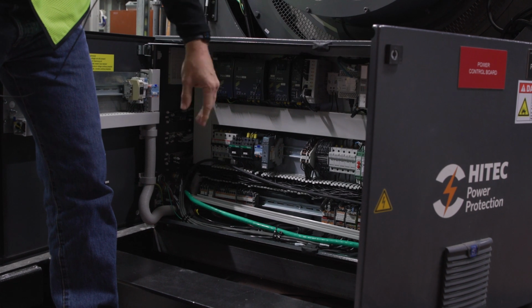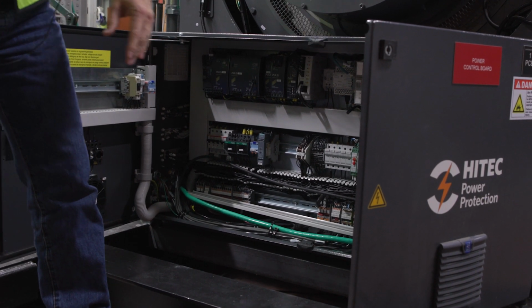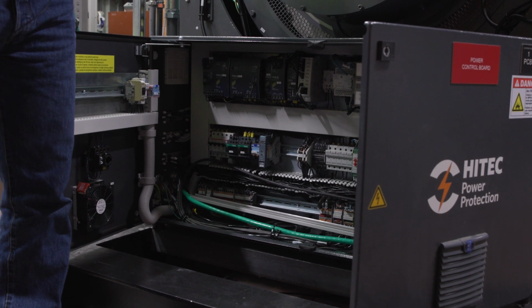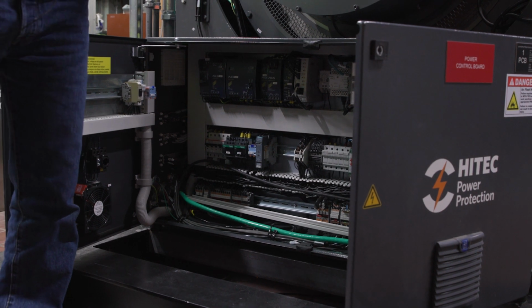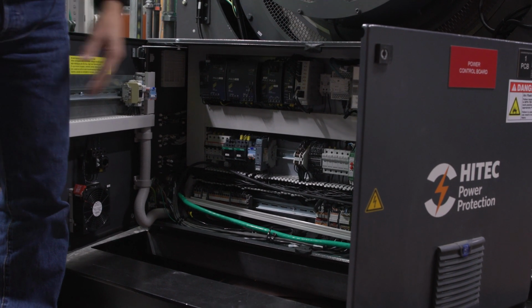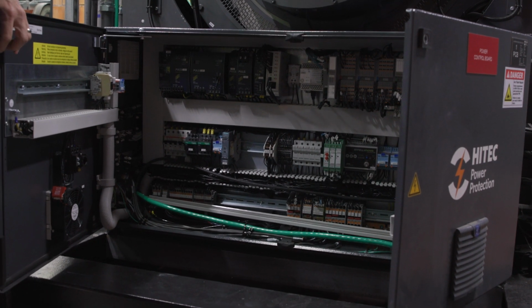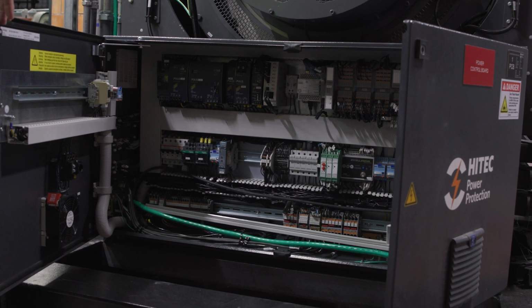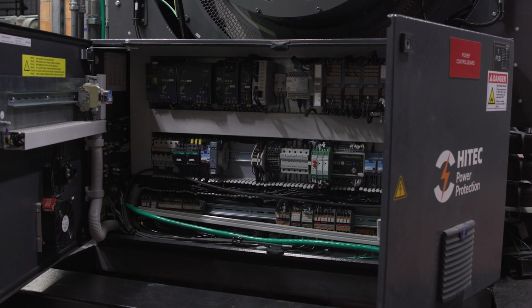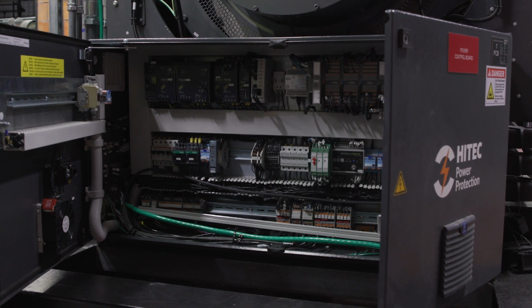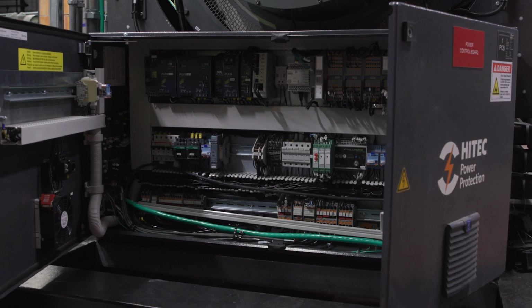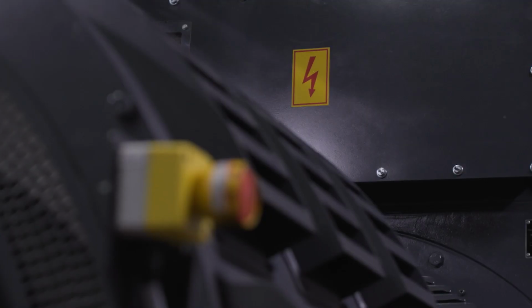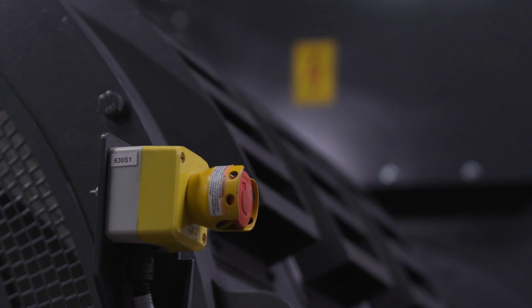So through this device, our PLC can communicate with this panel and be used to control things like diesel speed, AVR of the generator, and so forth. All of our sensors from our temperatures, vibrations come into here as well. This little device, this IntelliNova device, is basically measuring the vibrations of the unit. So again, all the interfaces we need from the UCP to the PGM come through this box. All sensing points from the PGM to the UCP go through this box, and all the network connections and so forth. We have 2 additional e-stop buttons, one on each side of the pony motor. So these buttons will function the same as the UCP e-stop function. They all operate the same way, just push them if you need to.